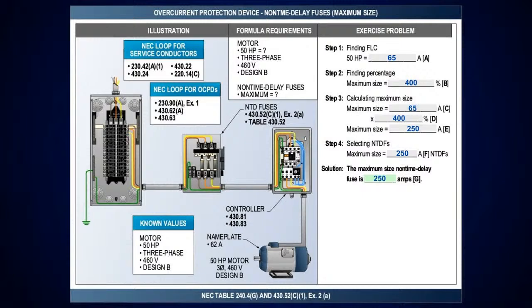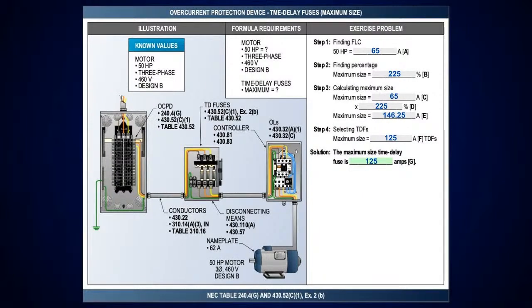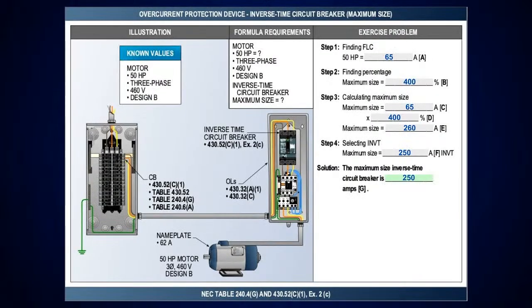Okay. Now, if I come over here and I look at my time delay fuses, and you come down and you pick up your time delay fuses, it tells you it's permitted to be increased, but in no case shall it exceed 225%. So I take 65 amps at 225%, it's 146.25 amps. The next size below that, per Table 240.6(A), where your standard overcurrent device ratings are, that'll be a 125 amp overcurrent device. And then when I get to my inverse time circuit breakers, exactly the same thing.